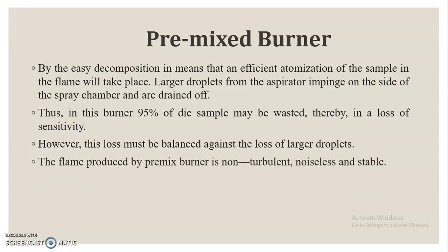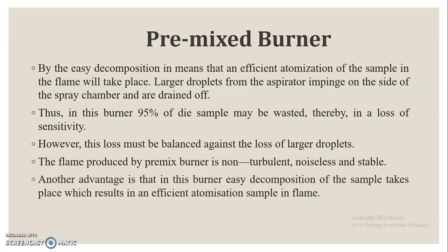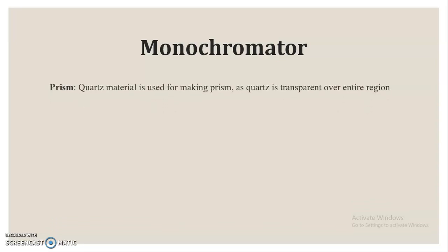The flame that is produced by the premixed burner is non-turbulent, noiseless and stable. So this is the advantage of premixed burners. Another advantage is that in this burner, easy decomposition of the sample takes place, which results in efficient atomization of the sample. The next component that is used in atomic absorption spectroscopy is the monochromator.